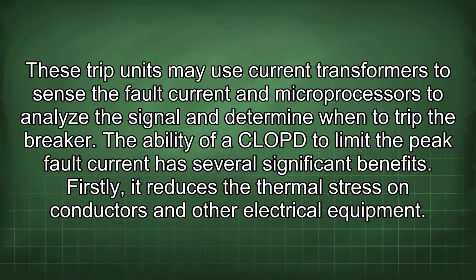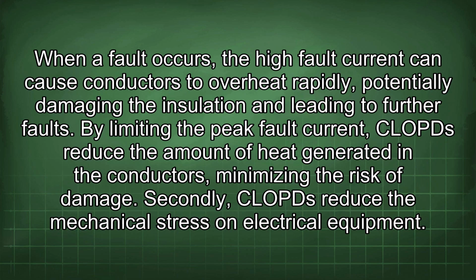Firstly, it reduces the thermal stress on conductors and other electrical equipment. When a fault occurs, the high fault current can cause conductors to overheat rapidly, potentially damaging the insulation and leading to further faults. By limiting the peak fault current, CLOPDs reduce the amount of heat generated in the conductors, minimizing the risk of damage. Secondly, CLOPDs reduce the mechanical stress on electrical equipment.